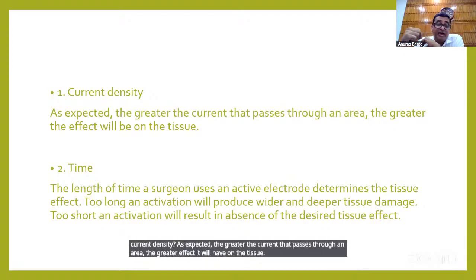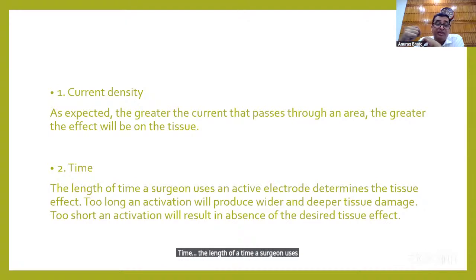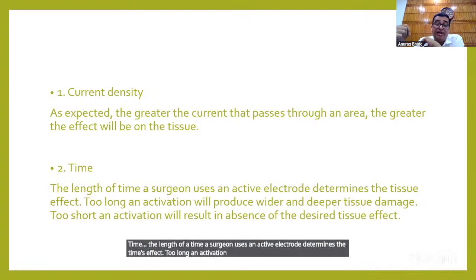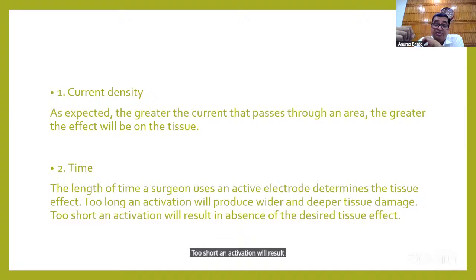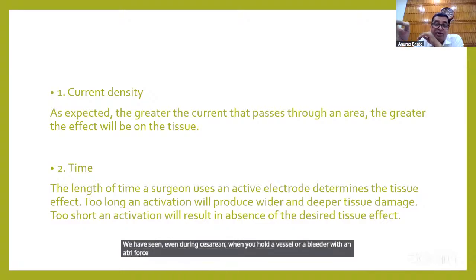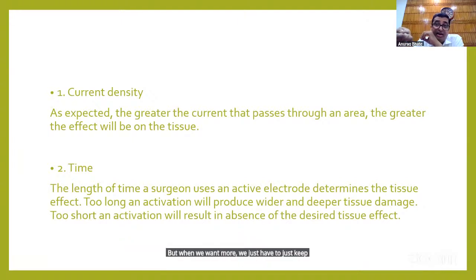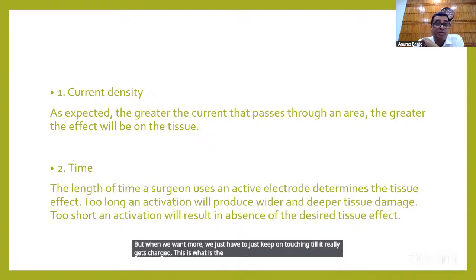Time. The length of time a surgeon uses an active electrode determines the effect. Too long an activation will produce wider and deeper tissue damage. Too short an activation will result in absence of the desired tissue effect. We have seen even during cesarean, when you hold a vessel or a bleeder with an artery forceps and then touch your cautery current to it, if it is just for a shorter time, we tell the residents, touch and go, touch and go, so that the slight amount of current will desiccate only minimal tissue. But when we want more, we just keep on touching till it really gets charged. This is what time does to the tissue.